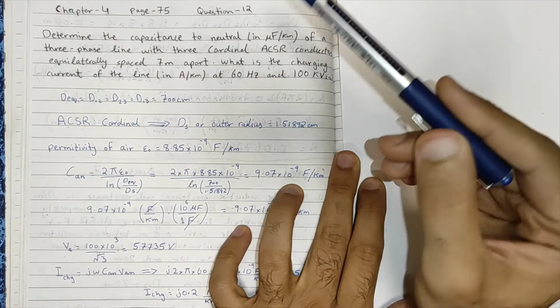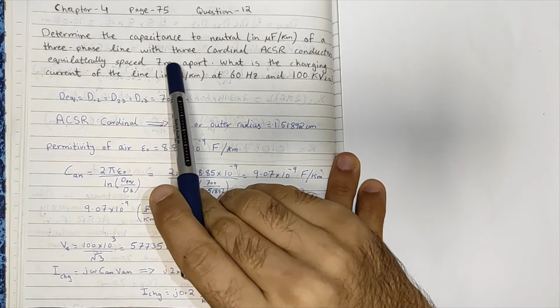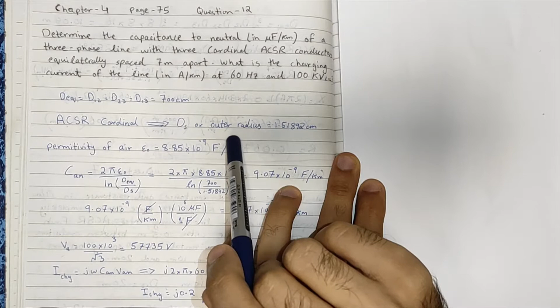Because it's mentioned in the question that the conductors are equilaterally spaced, it means that D1 equals D2 equals D3, which will be 7 meters or 700 centimeters, which will be the same as our D equivalent. And because it is Cardinal ACSR, we can get the DS from the table, which is the second column, or the outer radius column. Remember, we will use the outer radius in case of capacitance. So the outer radius from the table for Cardinal will be 1.51892 centimeters.